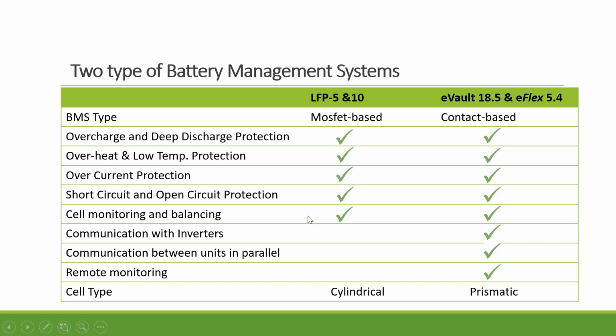But if you do smaller systems, the 5 and 10 work well. They all protect the cell from overcharging or over discharging, and protect them from overheat and low temperature. It also has overcurrent protection, like a breaker and fuse, as well as protection against short circuits or open circuits. The BMS will also disconnect to make sure that inverters will not overpower the battery cells.